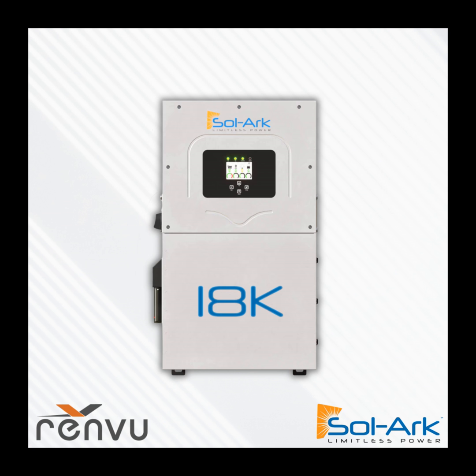Our system architecture, typically for residential: the Sol-Ark goes between the meter and the main service panel. This is the standard residential configuration. Solar wires up, the load side wires up, the batteries wire up. You have that bonus port for a variety of devices, but you have to pick one, and then the grid side comes in and lands on the Sol-Ark. You do need to add an external disconnect.